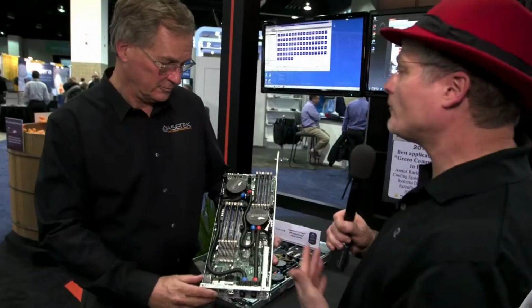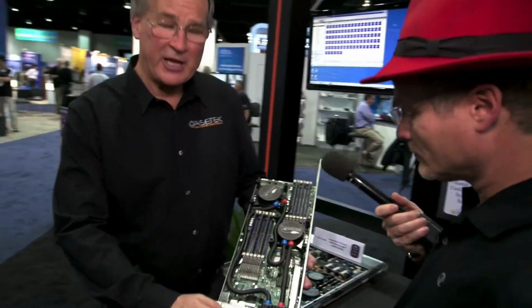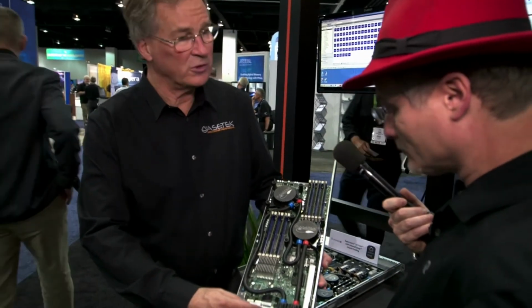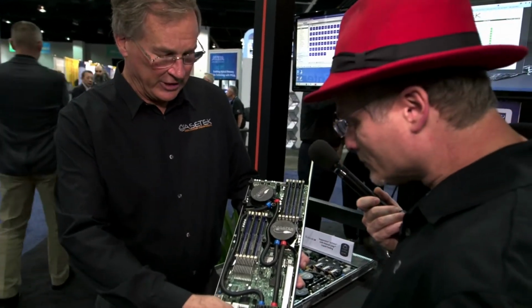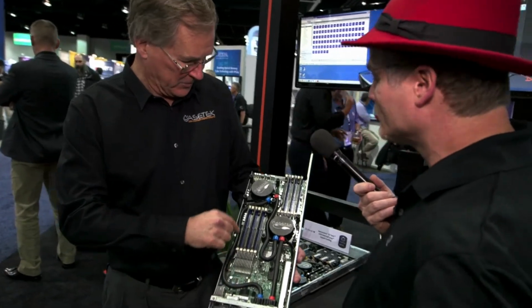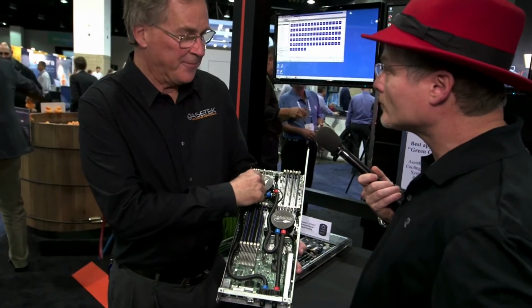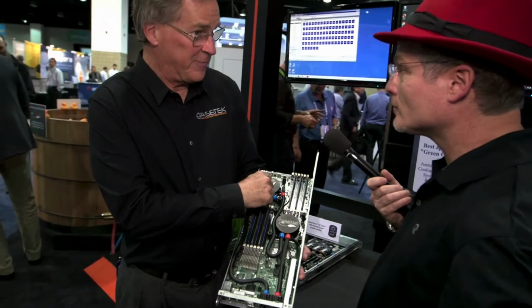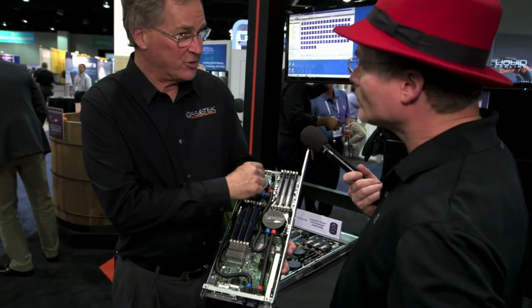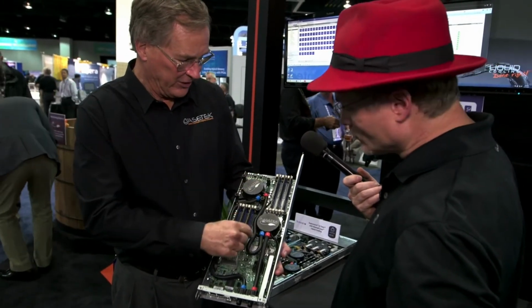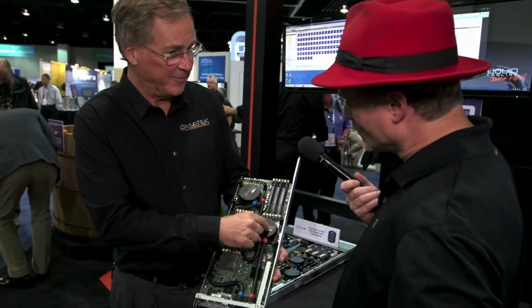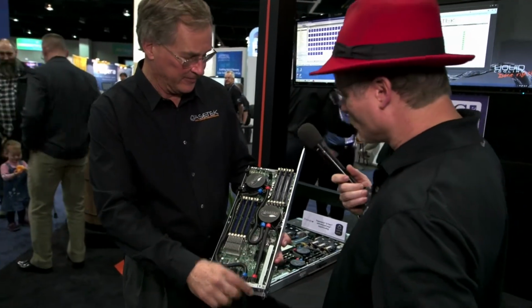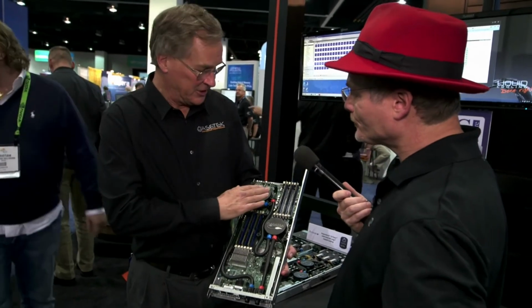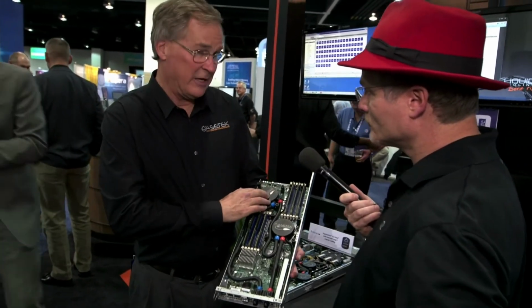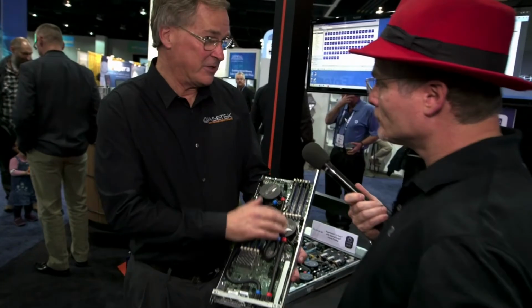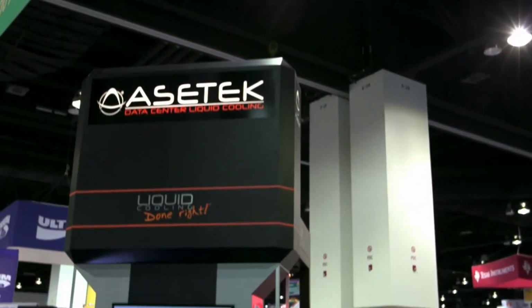All right, Steve, what are we looking at here? So, Rich, this is a direct-to-chip liquid-cooled server. What we're doing is bringing warm water in here up to this circulation pump, which sits right on top of a CPU, with a cold plate on the bottom. So, cooling this first CPU, bringing the warmer liquid down through the second pump and CPU cooler and out the back here. What's nice about this system is it's got two pumps in it, and they're in series. Either pump is capable of driving the system, so we've got redundancy.